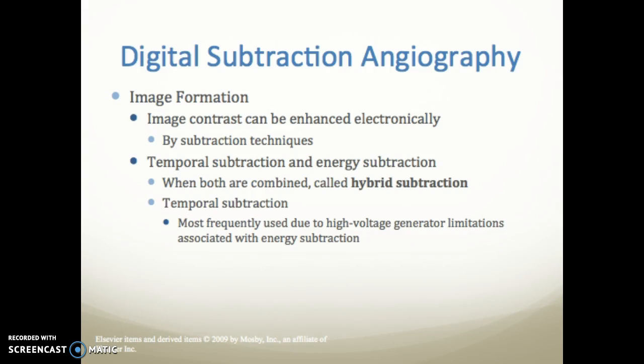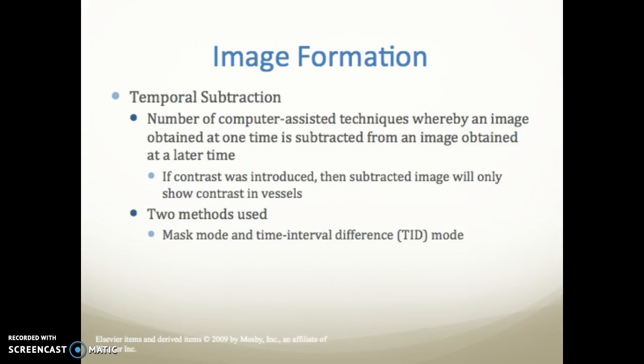Image contrast can be enhanced electronically by subtraction techniques. There are two types: temporal subtraction and energy subtraction. When both are combined, it is called hybrid subtraction. Temporal subtraction is more frequently used due to high-voltage generator limitations associated with energy subtraction. There are two subtypes of temporal subtraction: mask mode and time interval difference mode.